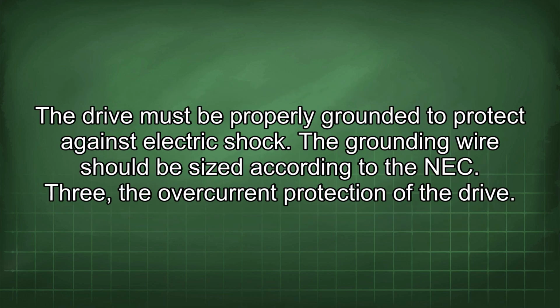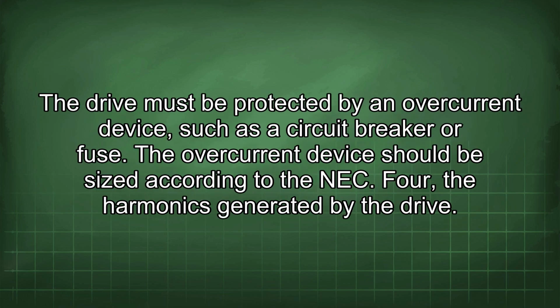The drive must be properly grounded to protect against electric shock. The grounding wire should be sized according to the NEC. Three: the overcurrent protection of the drive. The drive must be protected by an overcurrent device, such as a circuit breaker or fuse. The overcurrent device should be sized according to the NEC.